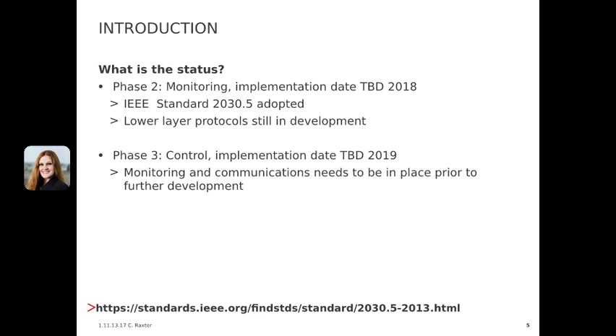To talk about Phase 2 with monitoring, the Institute of Electrical and Electronics Engineers, IEEE Standard 2030.5, has been adopted for Phase 2 monitoring. However, the method for achieving this standard, which is the lower protocols that actually communicate to the DER, is still being developed. With Phase 3, the monitoring and communication really needs to be in place before control could honestly be implemented. So the actual implementation date of Phase 2 will dictate when Phase 3 could potentially be implemented.